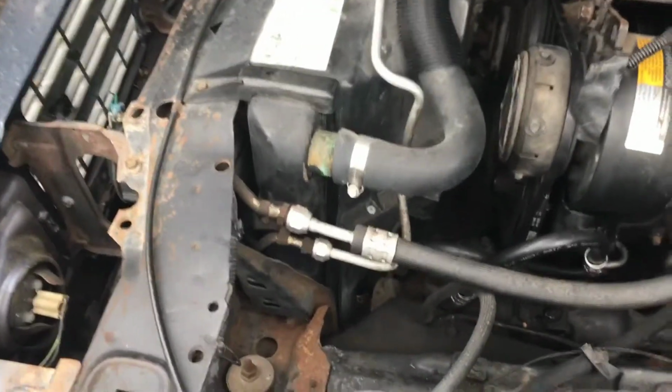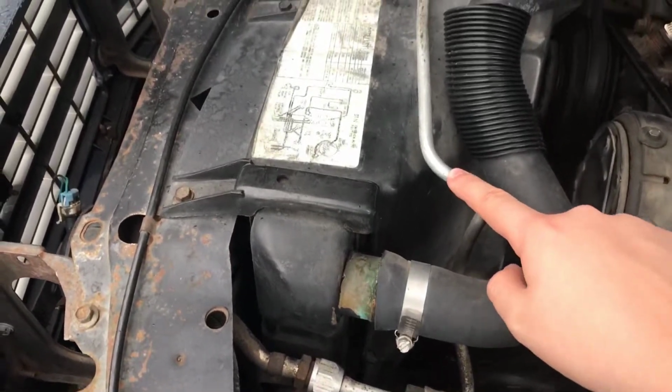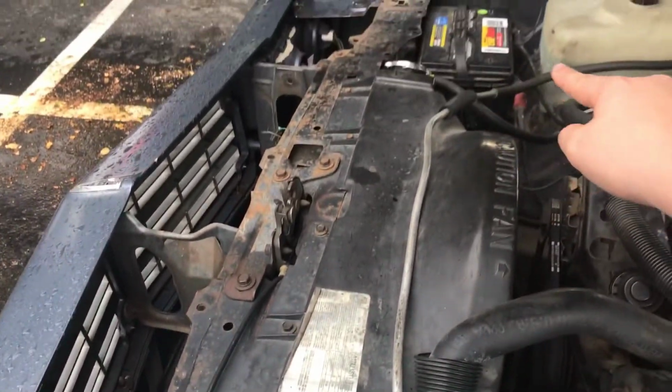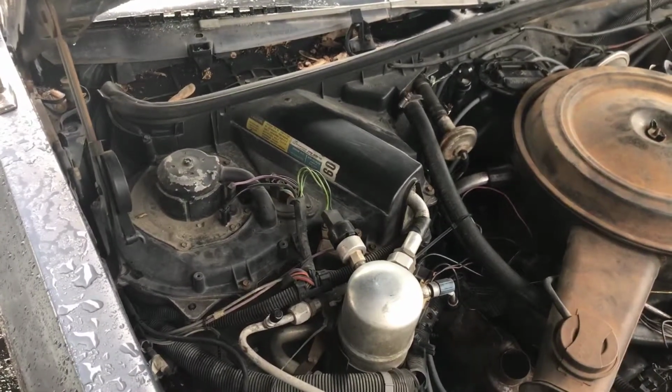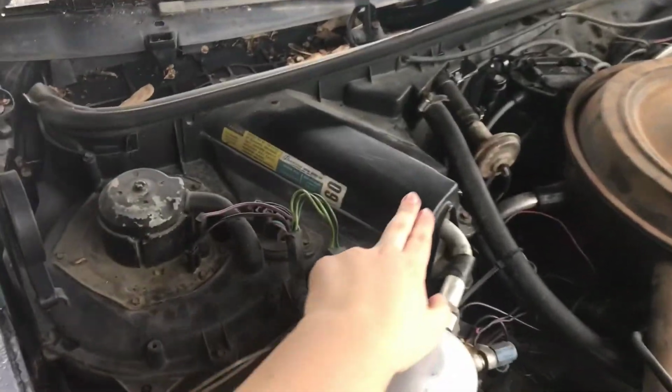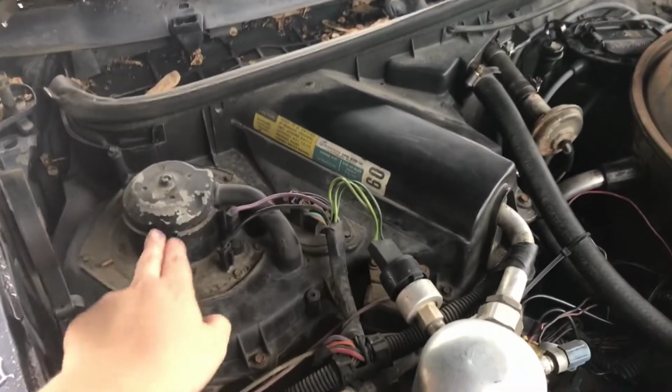The high temperature, high pressure liquid leaves the condenser and heads to the metering device further down. As the high temperature, high pressure liquid hits the metering device, which is simply an extremely small hole that mists the refrigerant, it turns into a low pressure, which equals a low temperature. Now it's still a liquid, just at a different pressure, till it hits the middle of the evaporator coil, where another fan is blowing air over it.